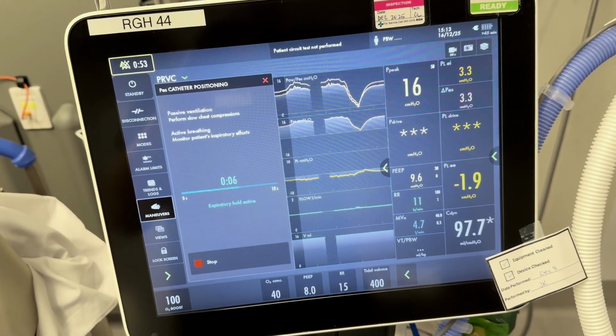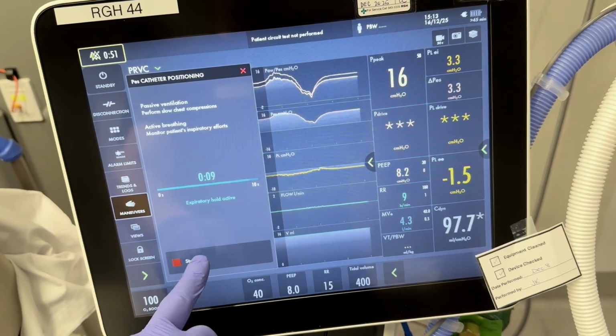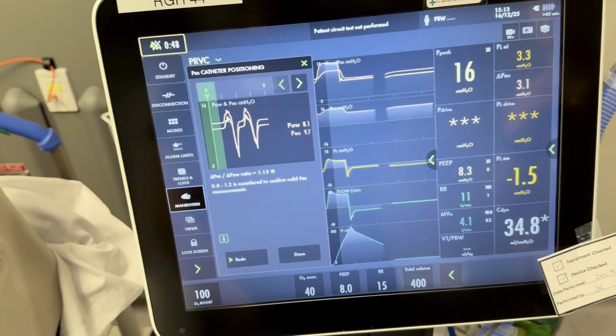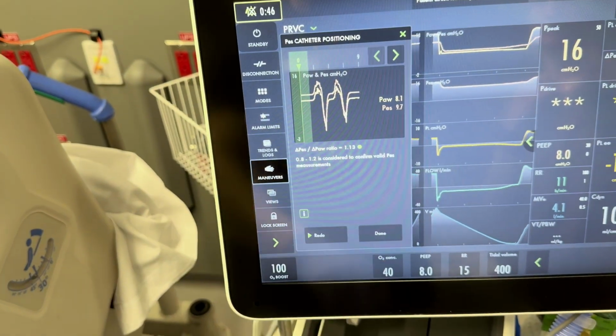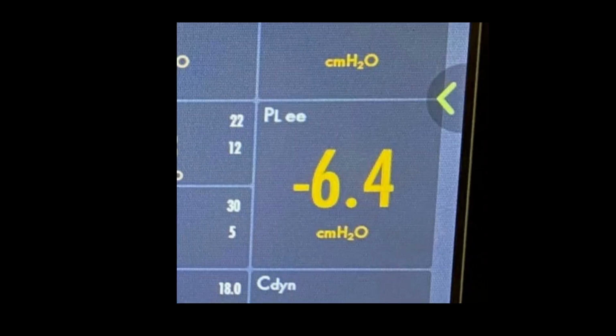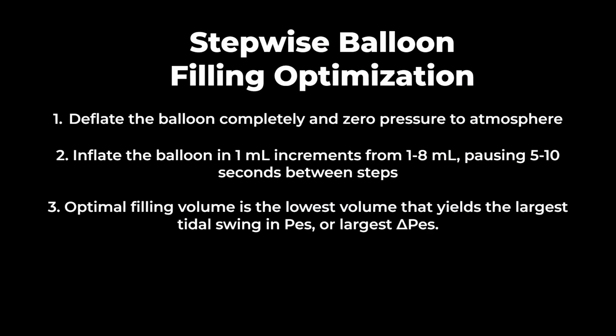If not, repeat the maneuver while compressing a different spot on the chest and confirm position of catheter on X-ray. If it continues to fail, observe the displayed end-expiratory transpulmonary pressure. If it is significantly below 0, then increase PEEP until end-expiratory pressure is closer to 0. Allow it to stabilize, then repeat the maneuver. Significant airway collapse can prevent proper measurement of end-expiratory alveolar pressure. If it continues to fail, or cardiac oscillations are not strong, a stepwise balloon filling optimization may be required.